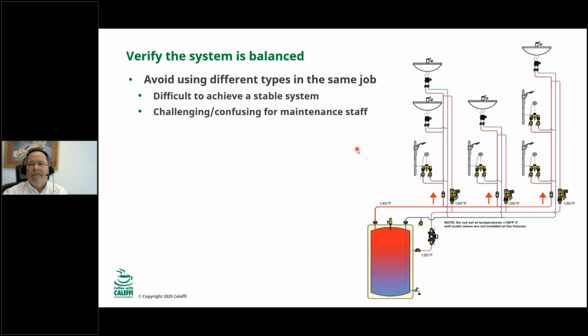That's a best case scenario. That's more like they do it in Europe, where you recirc as close to the fixture as possible. The stub out is actually a U fitting that you recirc past. That's probably the absolute best way to do it. It's a completely different amount of pipe for that project, and we haven't really seen that type of system adopted yet. But if that's what they're enforcing in Wisconsin, you're going to have to recirc like that. What we're showing is the laterals there. You'd have to recirc past those, which is a lot more pipe, but it is good practice to have the minimum amount of stagnant water potential in the run out.